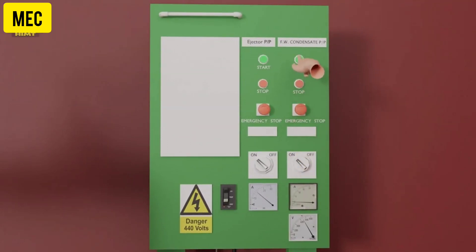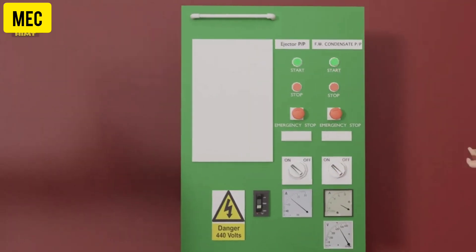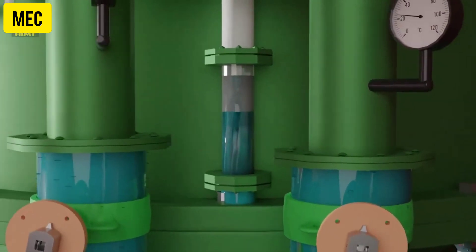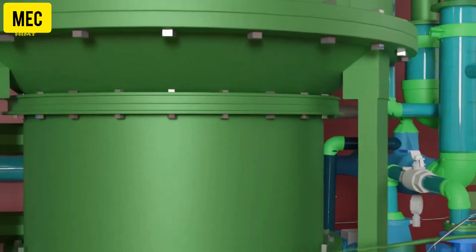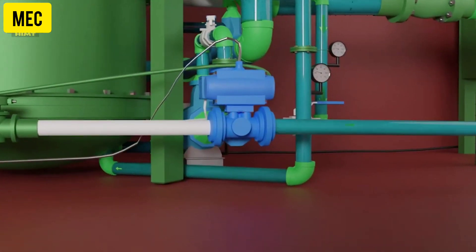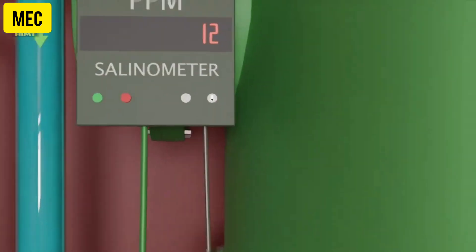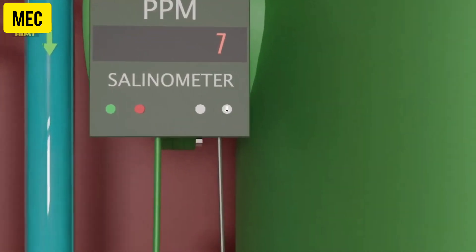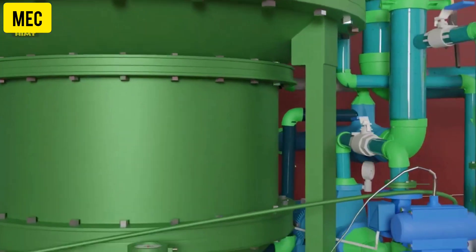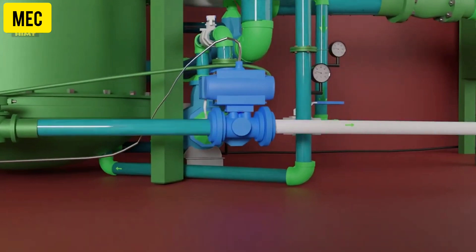Now regulate the discharge valve of the ejector pump to maintain the water level at half of the gauge glass. After that, observe the salinometer reading which is set to give an alarm when the salinity of the distillate exceeds 10 ppm. When the salinity is more than 10 ppm, the three-way valve transfers the distillate either to bilge well or back to the freshwater generator shell. When the salinity drops to less than 10 ppm, the three-way valve transfers the distillate to freshwater storage tank.